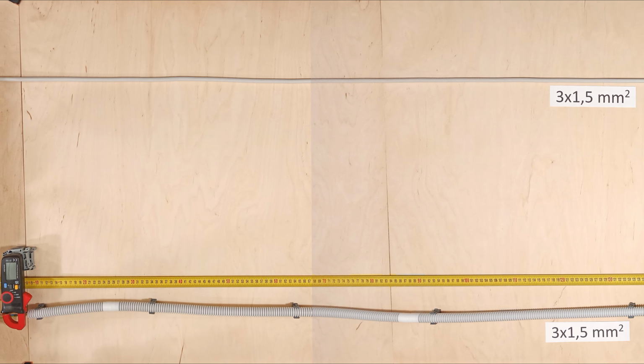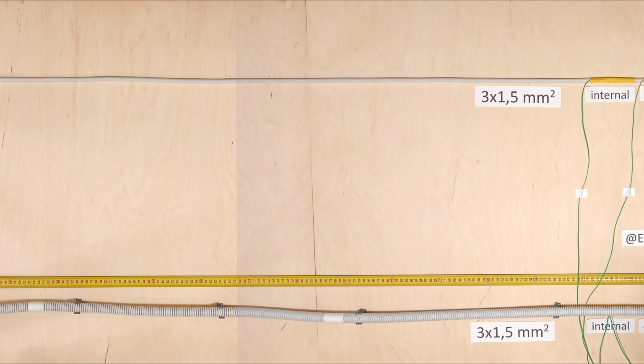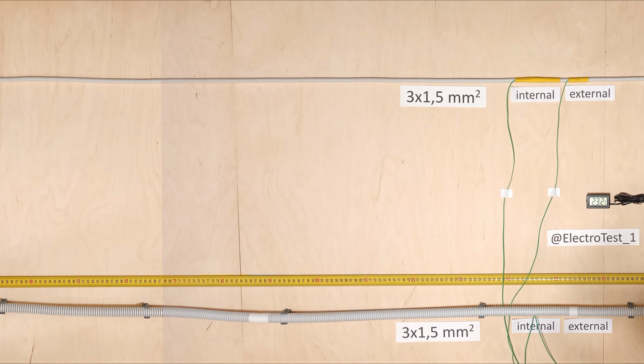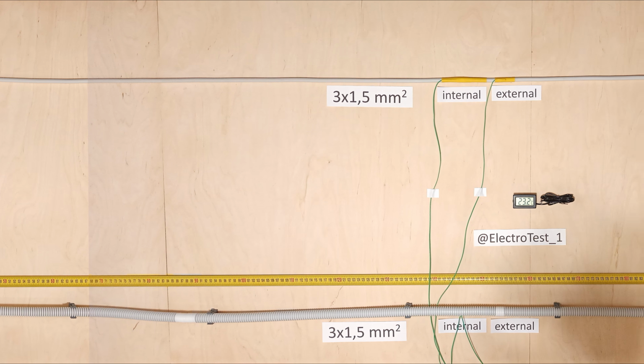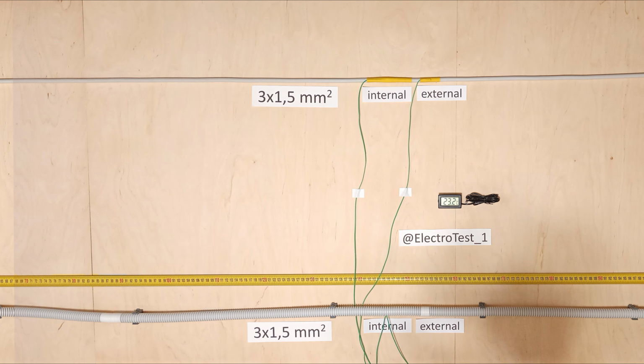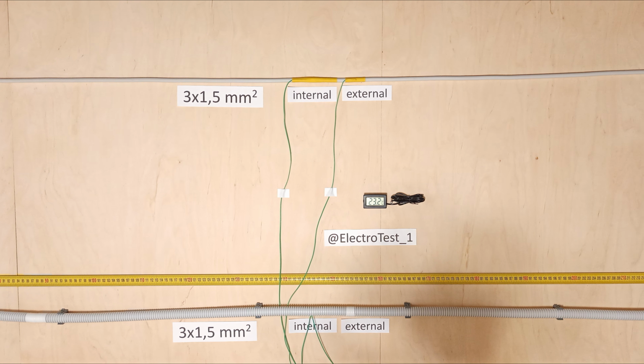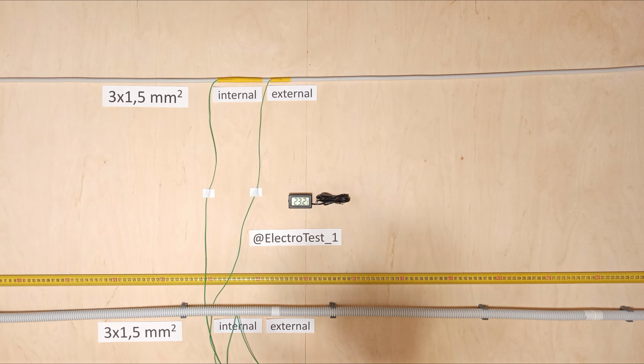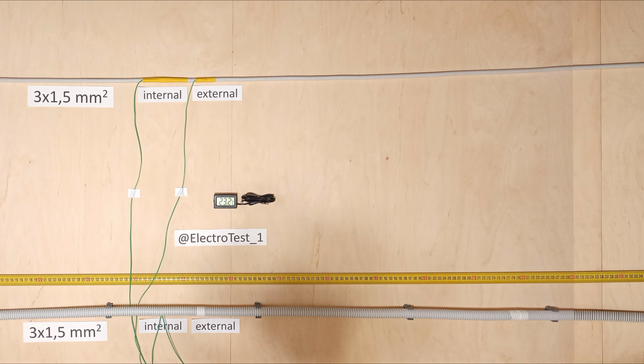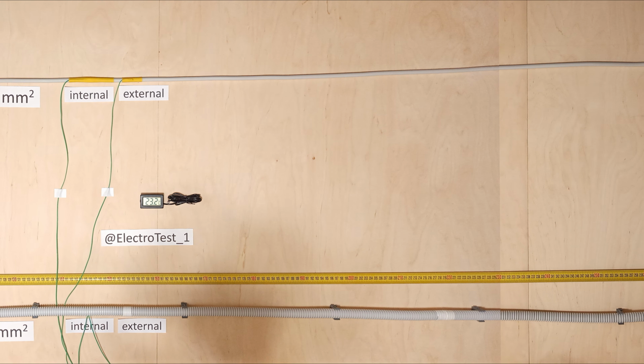Some conclusions. Inside the conduit, the cable heats up more, and this is especially noticeable at maximum permissible currents and during overload conditions. The temperature inside junction boxes always exceeds the internal cable temperature by about 5–10 degrees.